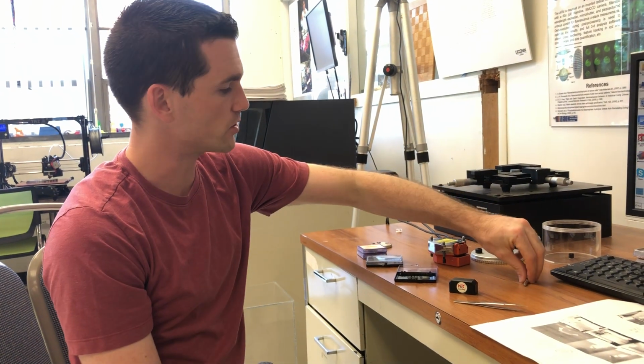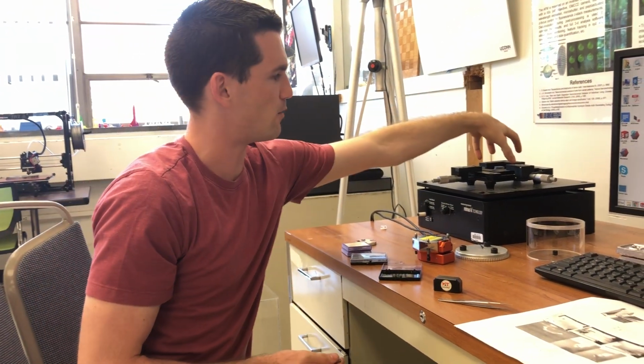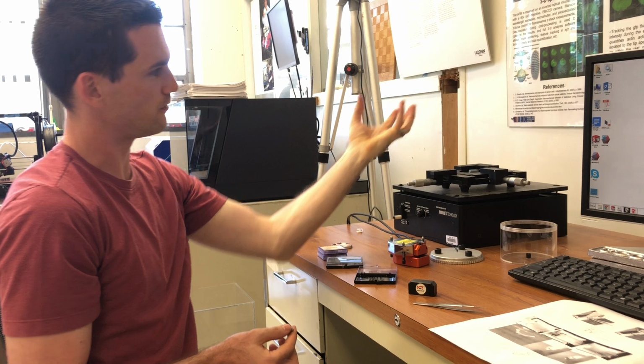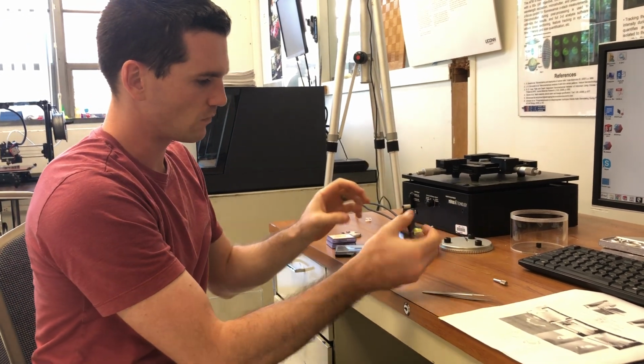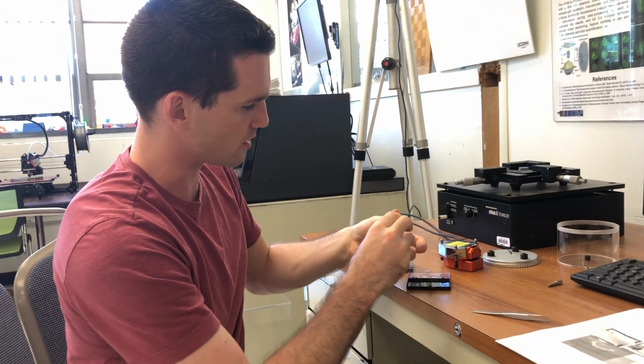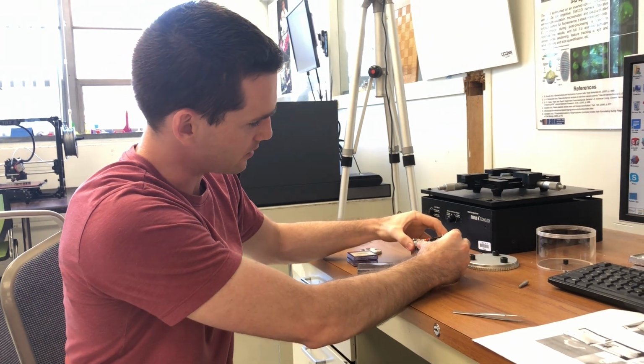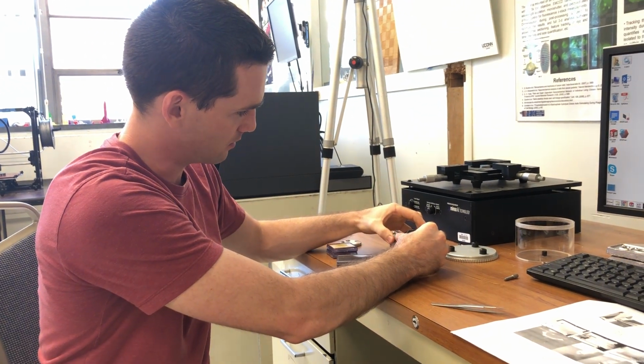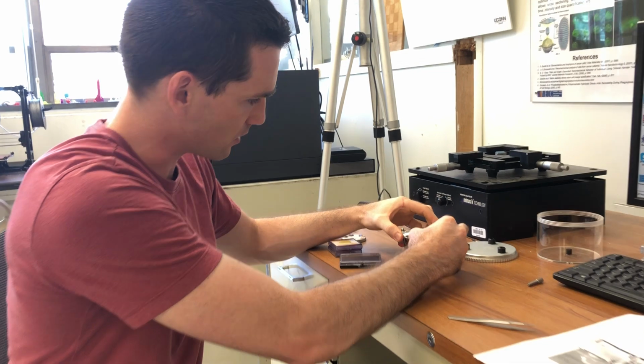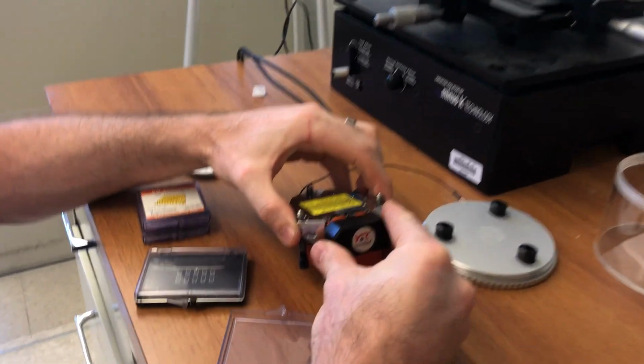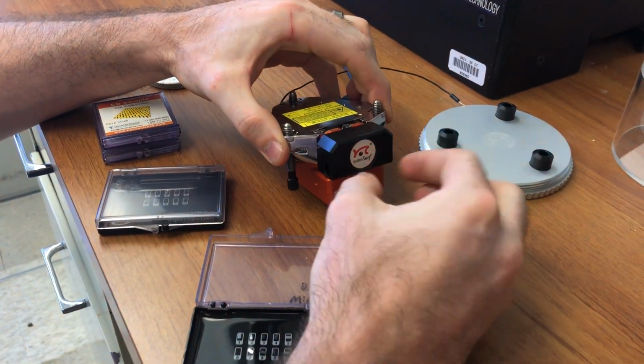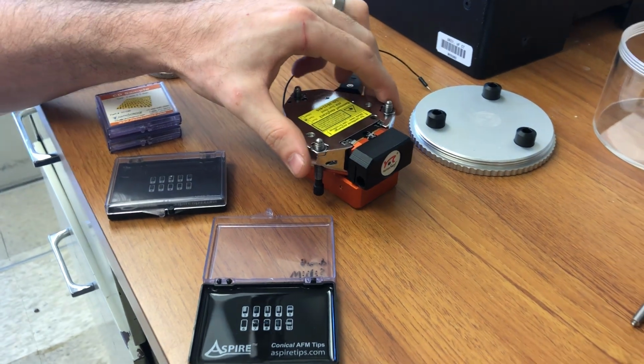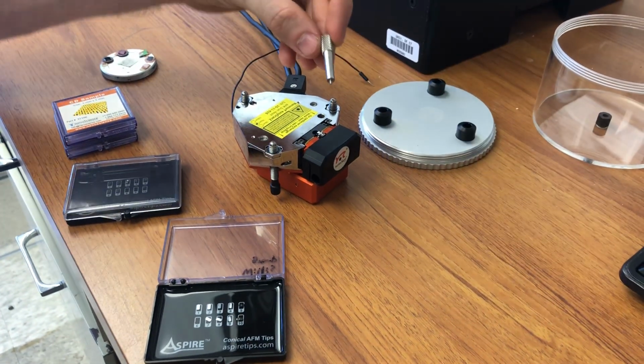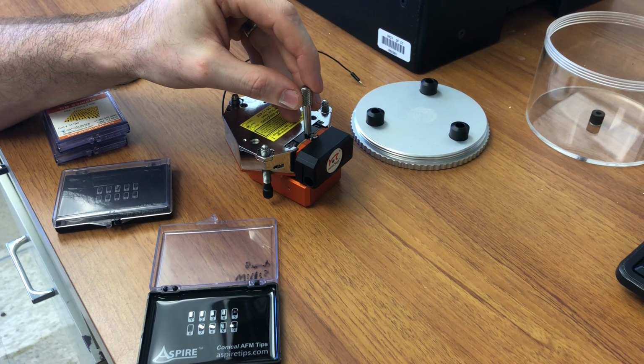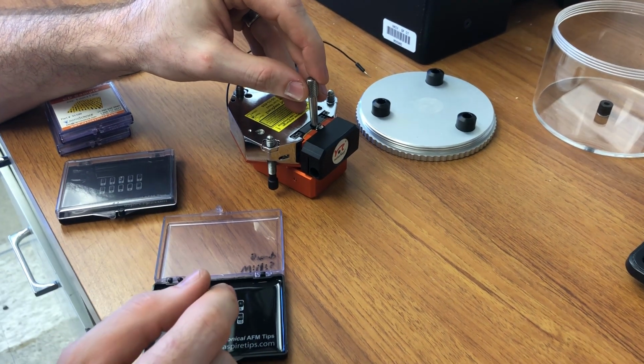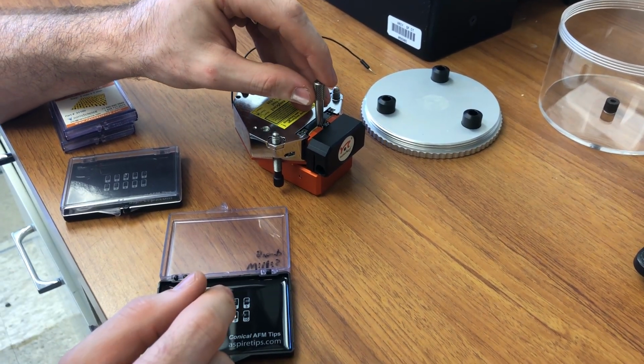So the process is essentially, we take the AFM off of the top here, flip it over. We put this laser block onto this end piece like this. It just slides over, so it's blocking the laser light from getting in our eyes. Just like that. We'll take this little pin and put it in the hole here. You see it makes contact with the tab and lifts up with a little spring.